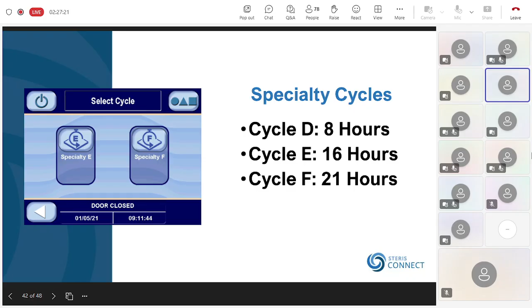The testing that was done with Formlabs and STERIS was all submitted to the FDA for their clearance and their 510K certification. So that's why the cycles are so long. It's about aerating the devices so that there is no vapor hydrogen peroxide left in the device which could damage the patient. The cycle claims, basically, there are limits on weight, which is 2.3 kgs of device in the chamber. And whether you are doing cycle D, E or F, you'll see that there are lumen dimensions, lumen inner diameters, and length of the devices. So this information is available for us to provide to you. If you need this information, we are very, very happy to provide it.